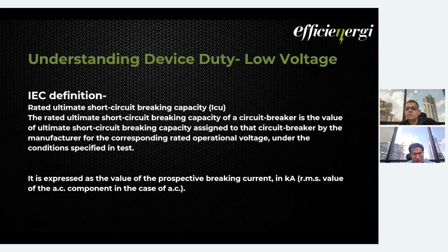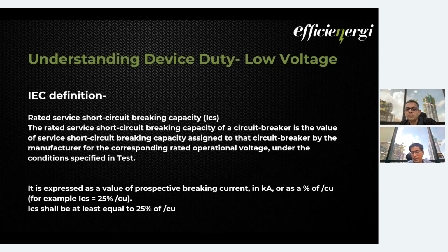Again, it is expressed as a prospective breaking current, in kiloampere. So we know 50 kiloampere, 65 kiloampere, that's what we see on the breakers. Then we have ICS. The ICS breaking capacity is assigned to the circuit breaker by the manufacturer, corresponding to an operational voltage, under conditions specified in the test. This word is basically important. How it is important, we'll cover in the next slide, when we see the difference between ICU and ICS.